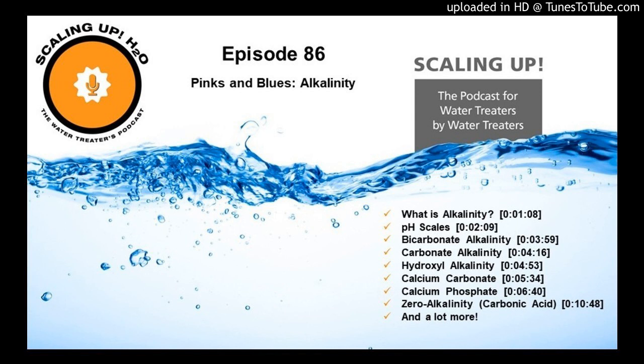It doesn't really stick to each other. And then we have some sludge conditioners in there to prevent it from doing that. And we can get that out through normal blowdown. Calcium phosphate, we have to get out through some very difficult means. So that's why you want the OH alkalinity in the boiler.